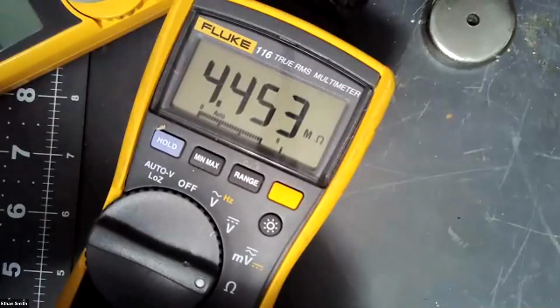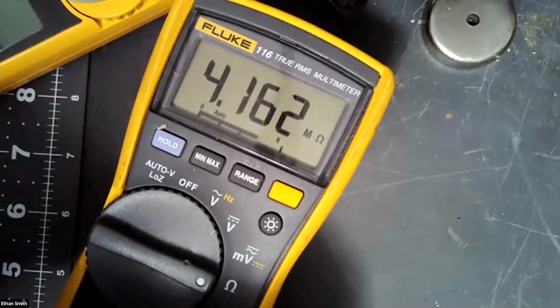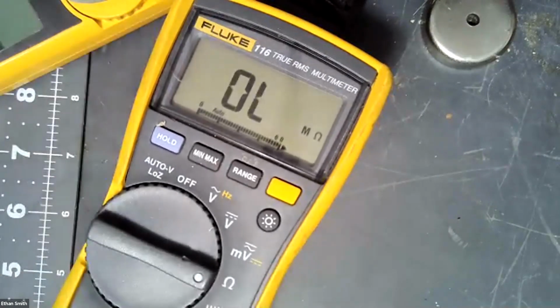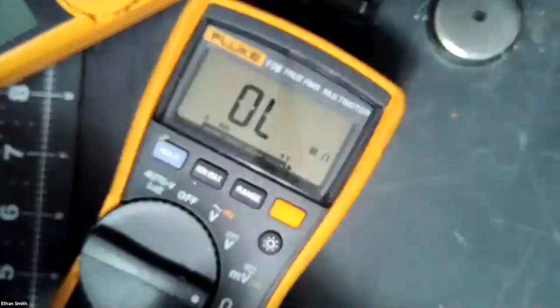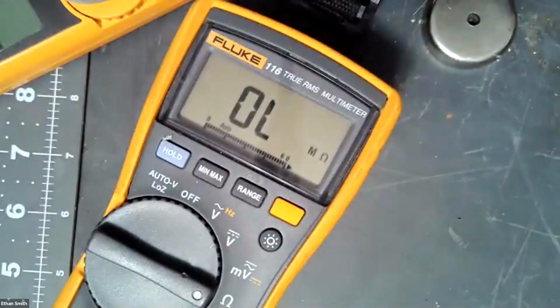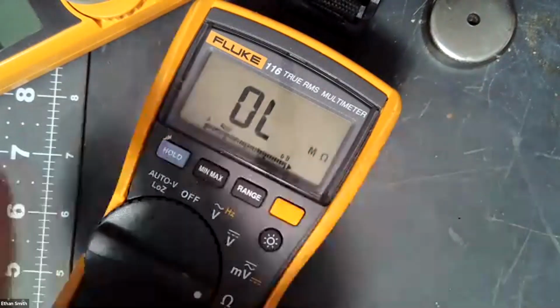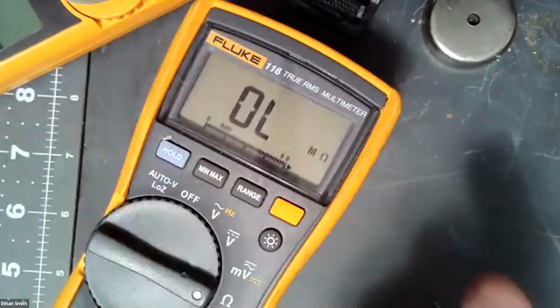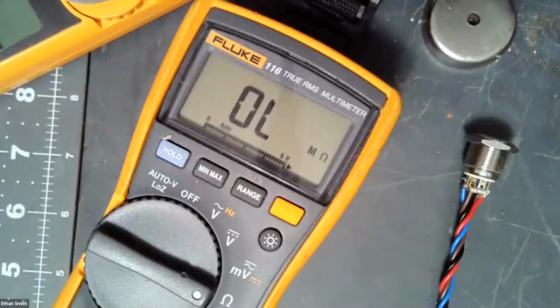What it's doing is, if I go through one direction of the diode, I'll get resistance through it. If I go the other direction, it's just open line. So there's the other direction here, and I'm just reading OL. So that's another way you can test a diode. If you get resistance through both directions on the diode, you know your diode's bad. It's no longer acting as a check valve.